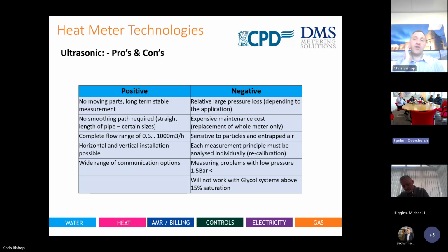Negatives: large pressure drop, depending on the application. It's determined by how you size a meter in relation to downsizing the profile. The ultrasonic meter is based around having a smoothing path, and on having that water velocity going through it. If you downsize too much, naturally you get a large pressure drop through a meter. So it's balancing what's best for price, the application, and selecting the correct meter, which we're there on a day-to-day basis for.